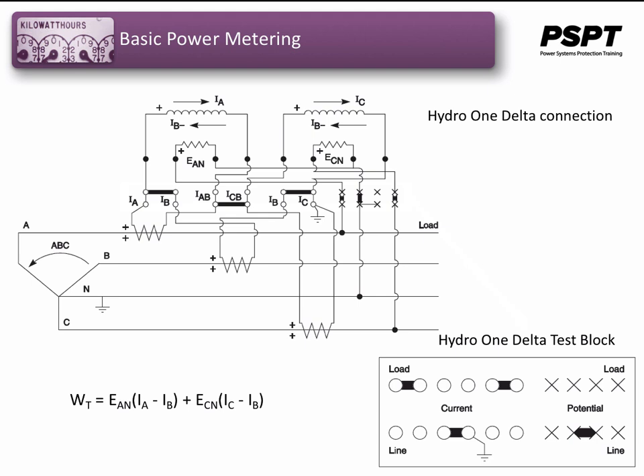Tracing the potential current flow, you'll see that it flows from line A to neutral and from line C to neutral in the left and right elements. If the neutral potential link was a normal fuse and it opened, the potential coils would be placed in series, and potential EAC and ECA would be applied to the potential coils. This would definitely cause errors in the measurement.